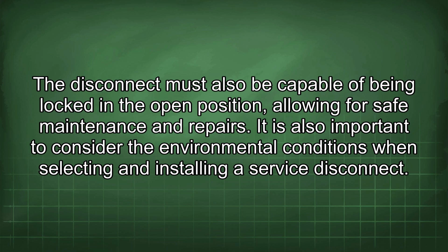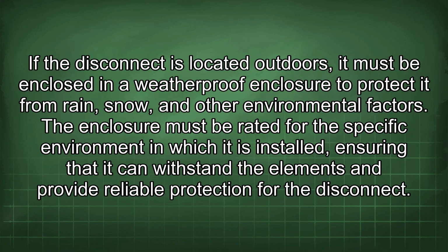It is also important to consider the environmental conditions when selecting and installing a service disconnect. If the disconnect is located outdoors, it must be enclosed in a weatherproof enclosure to protect it from rain, snow, and other environmental factors. The enclosure must be rated for the specific environment in which it is installed, ensuring that it can withstand the elements and provide reliable protection for the disconnect.